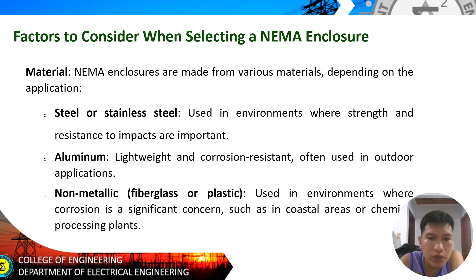Next is corrosion resistance. For environments where corrosive substances are present, like salt water or chemicals, a NEMA 4X enclosure made of corrosion-resistant materials such as stainless steel or fiberglass is ideal. So if your environment is near a beachfront or resort area, you can suggest to your client that NEMA 4X be used since it is corrosion resistant. These are simple things we can suggest to clients as engineers.